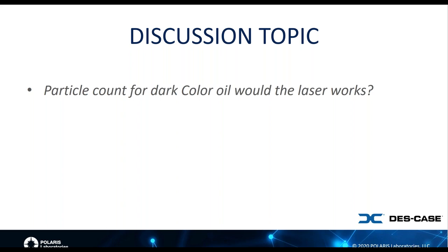Yeah, and you just want to keep in mind, if you're not filtering the fluid, particle count may not be the best option, and that's where we would probably recommend something more like a particle quantifier, where we measure your metallic content rather than just sheer volume of particles, because it may not be beneficial to what you're trying to figure out. Absolutely.